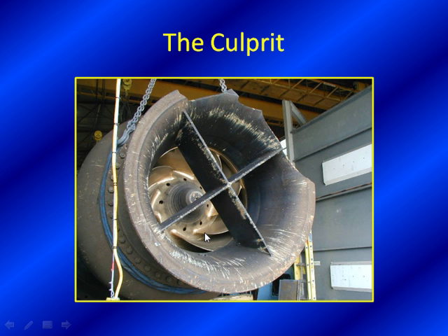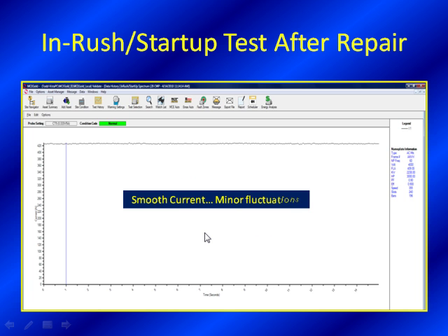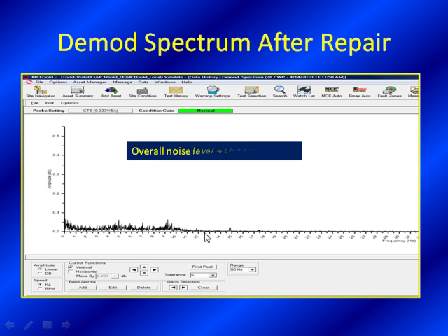After repair, the next best thing to do is take a follow-up test to verify that the maintenance and repair work was effective. You'll notice the amperage jumped back up to 420 amps. In previous tests the amperage had dropped - if the pump is not moving fluid efficiently, it's not going to draw as much power. So you can see the amperage is back up to normal steady state. And looking at our demod spectrum again, we were at 1 dB, and now we're back down to 2008 levels, which is exactly what we want to see.